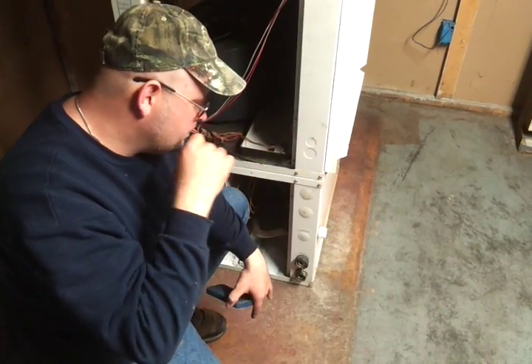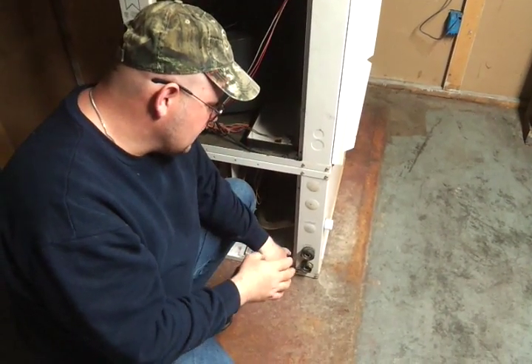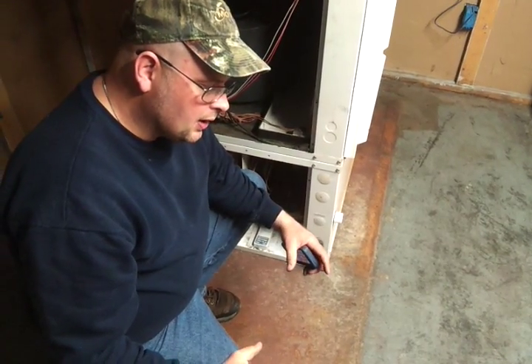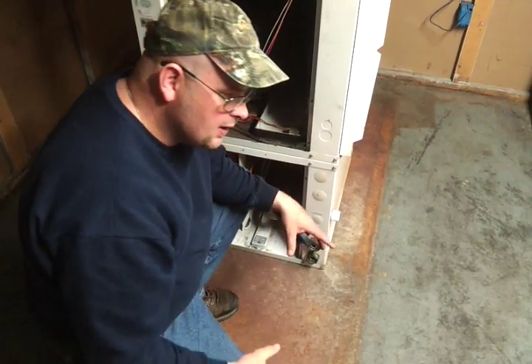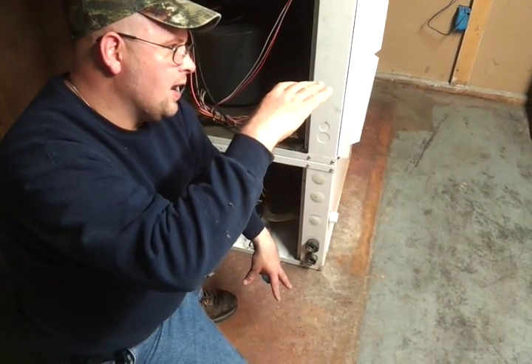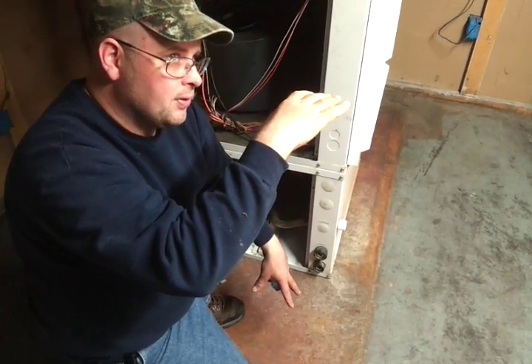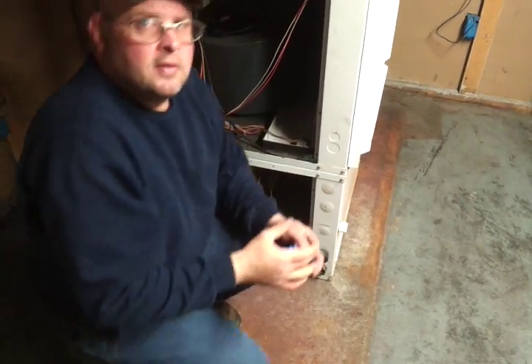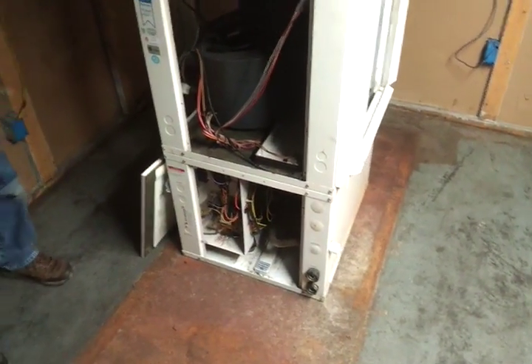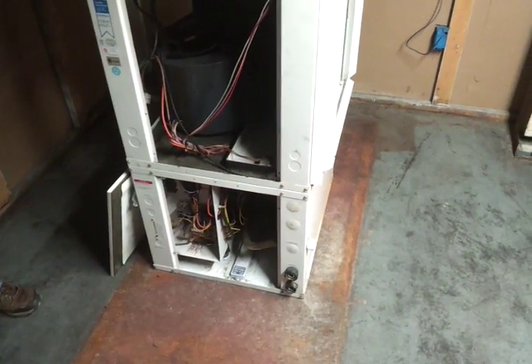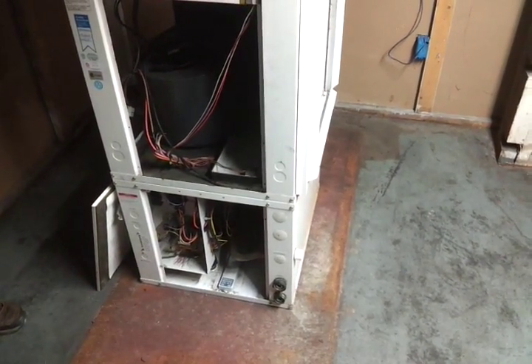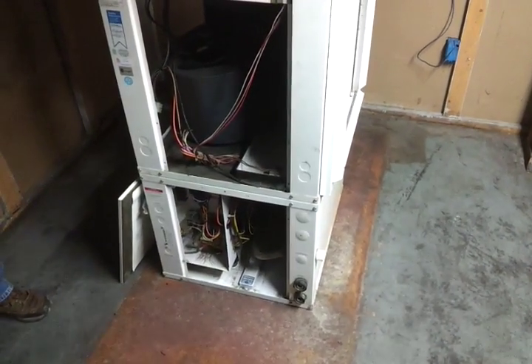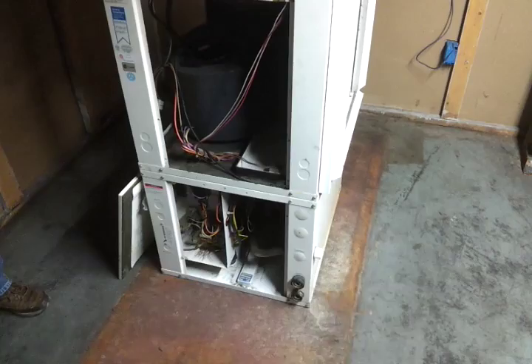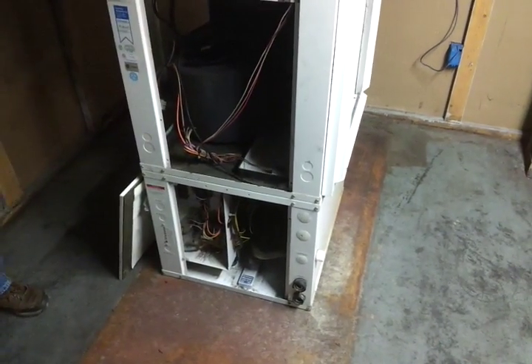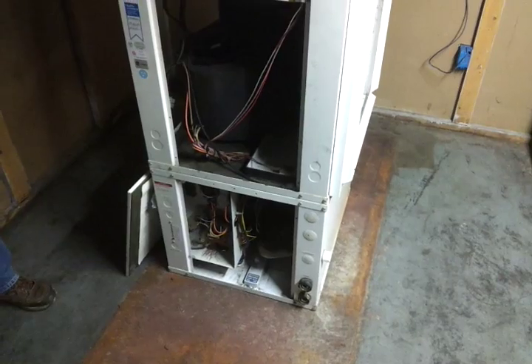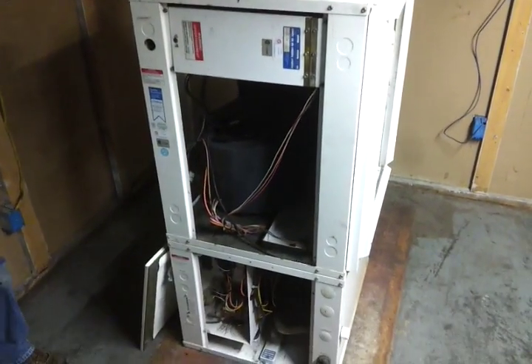What would be really nice to see is if you could get some threaded copper pipe, put your brass fitting in there, and get at least about 1.5 to 3 feet of copper from the furnace, to divert any of that heat before it gets to the PEX. If it does overheat, it's not going to melt the PEX. So we can use brass and copper hard pipe up to a point where, let's say up to here, would be safe. It would be like 6 feet. 3 feet minimum would be nice if you could do that. Kind of like the one downstairs. I don't know if you saw the one downstairs. They did it all copper. Now that's the way that I would do it, and that's kind of the way that they recommend to do it.